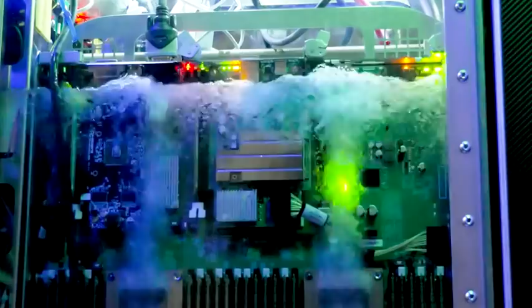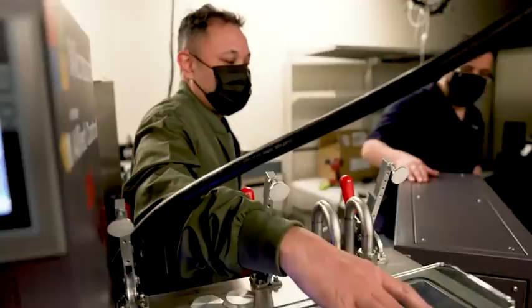With liquid cooling, we can have higher density racks and IT or tanks that could lead to smaller data center footprints, lower data center energy consumption from the mechanical cooling perspective, and also from the server perspective, because we could reduce or remove the fans from the servers, we could reduce the leakage current from the chips. Because liquid cooling utilizes closed loops of warm water, maybe counterintuitive, but we actually eliminate the use of water. We don't need to use evaporative cooling anymore because we're always going to operate in loops that are hotter than the ambient temperature.